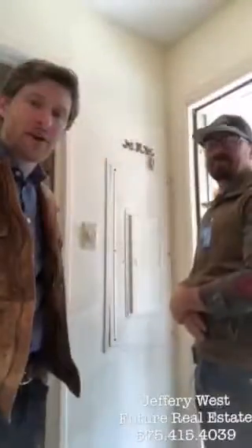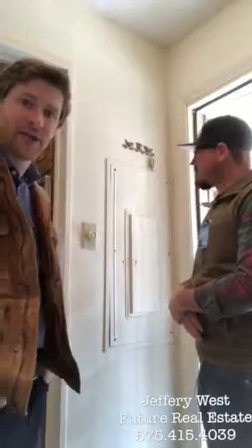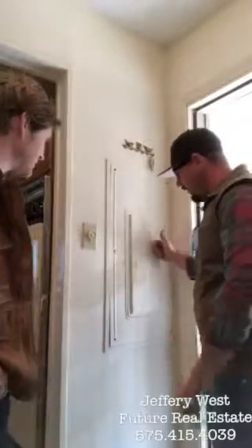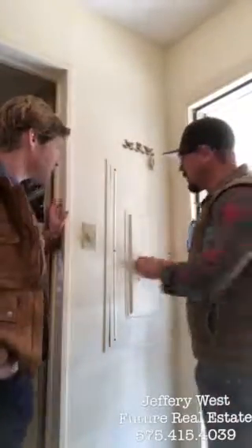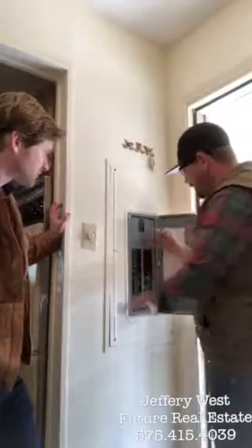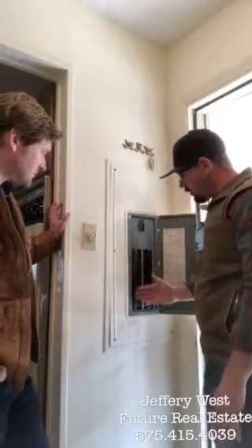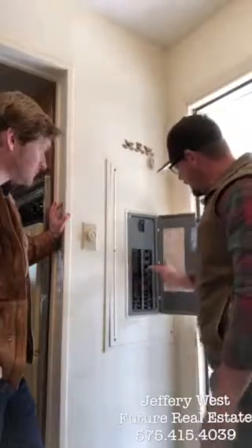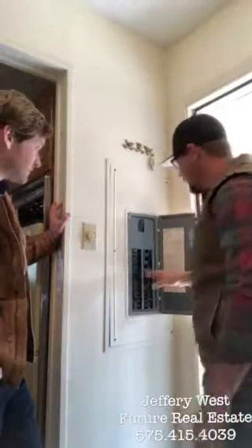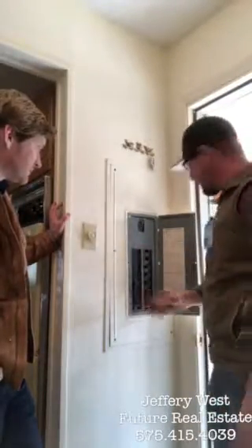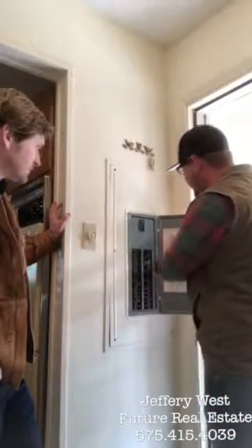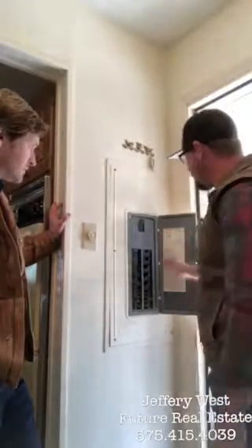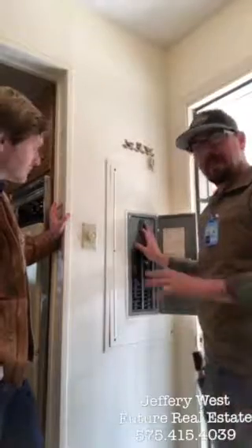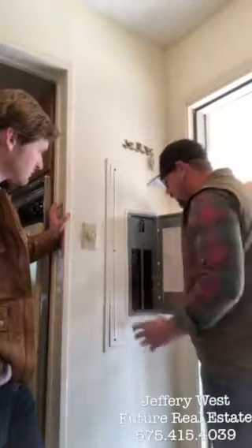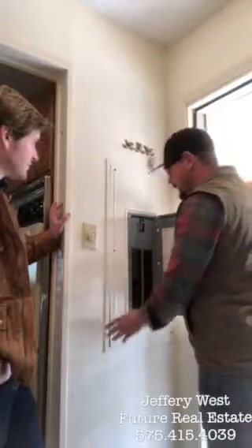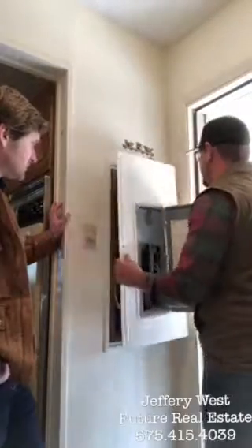All right, so we're up in the main part of the house to take a look at the electrical panel. Everett, what are you looking for here? First, we're gonna pop it open and make sure we don't have any open inserts or open blanks, so we can't stick our fingers inside the panel. We're also gonna look for the manufacturer. We have a Square D load center here with a 200 amp main breaker. Now we're gonna go into the panel and see what she looks like.